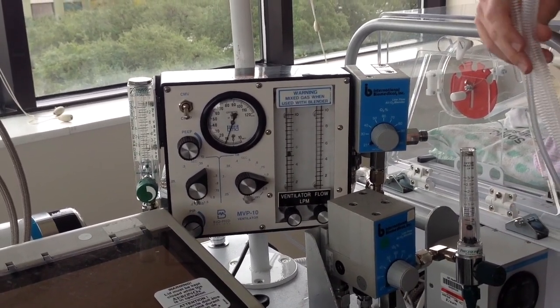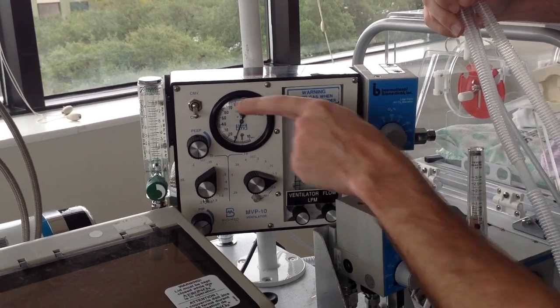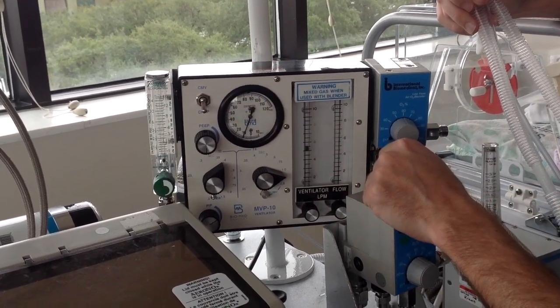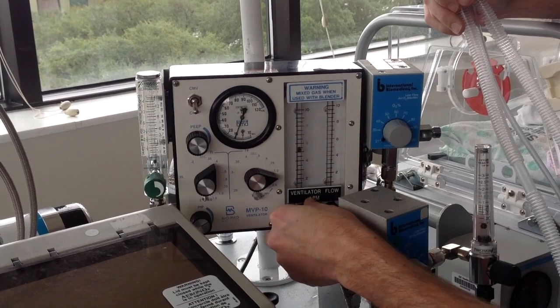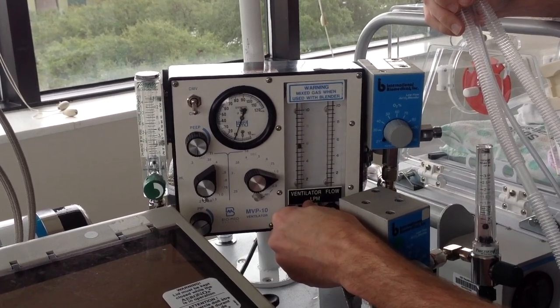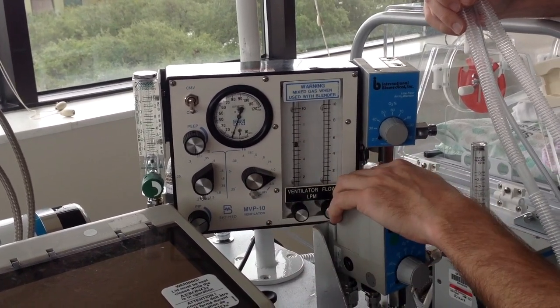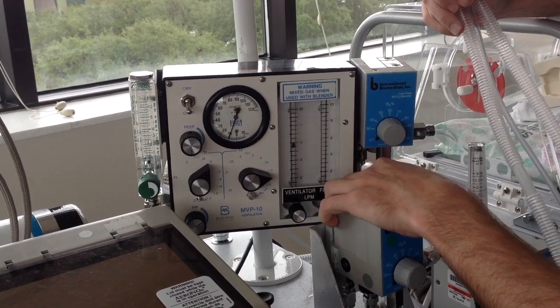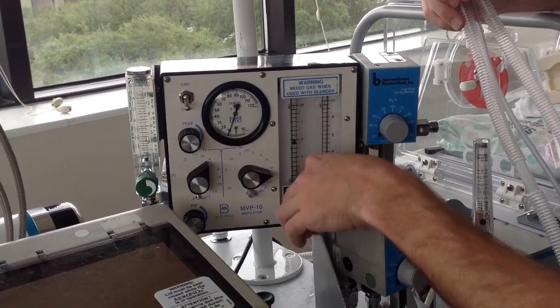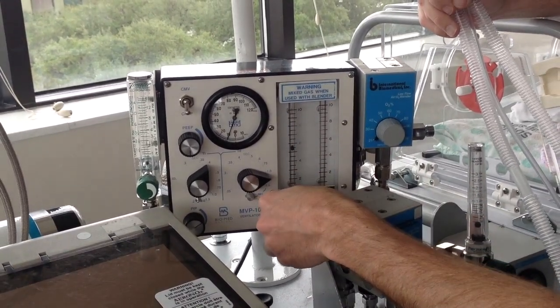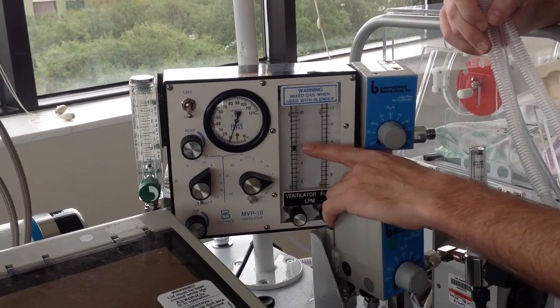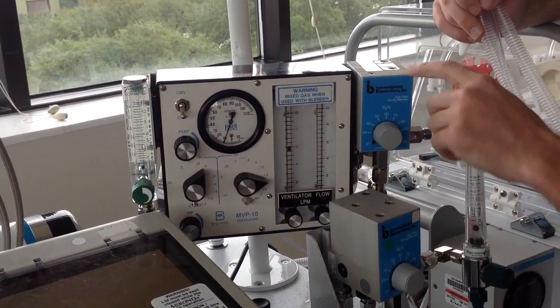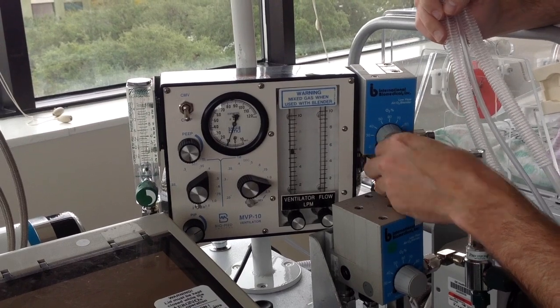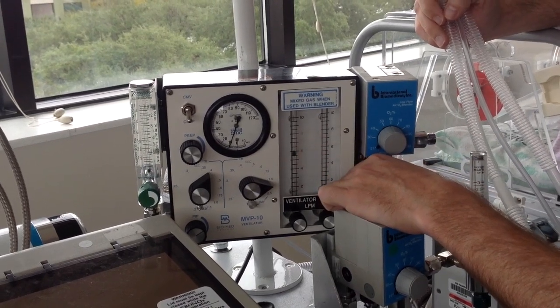So first off, let's just talk about our CPAP. So we're in our CPAP mode, continuous positive airway pressure. See, I gave us a flow of, let's say, 6 right here. You don't have to use both flow meters. For example, if that's a 6 right there and you want to do 6, you could do 3 and 3, right? But there's really no point for that because we're blending everything. So right now we're on 21% oxygen, flow 6.